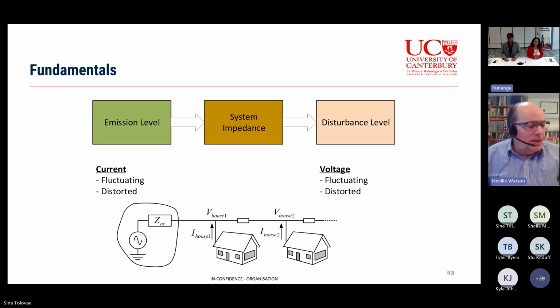I would like to just discuss this as a starting point, because the one thing we have to realize is it's the harmonic voltage that interferes with equipment connected. It's how far away the voltage is distorted from the ideal sine wave. However, the way we actually limit the distortion is the emission levels, and the emission is the current waveforms that either a load or a generator draws through the system. And of course, the thing that connects them together is the system impedance at that frequency. So that basically means if the system impedance is high, you can only allow a smaller harmonic current to flow to reach a given level of harmonic voltage.